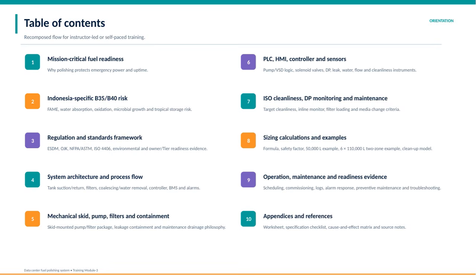This includes guidelines from agencies like ESDM, OJK, NFPA, ASTM, ISO 4406, and evidence requirements for environmental and owner or tier readiness. Then, we cover the system architecture and process flow, detailing components like tank suction and return lines, filters, coalescing and water removal units, controllers, building management systems, and alarm configurations. The next section focuses on the mechanical skid, pump, filters, and containment strategies, emphasizing skid-mounted packages, leakage containment, and the philosophy behind maintenance drainage.